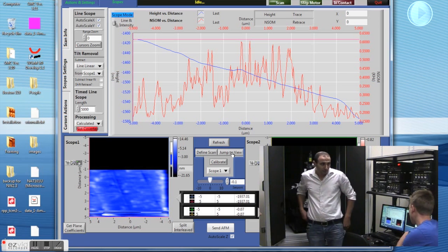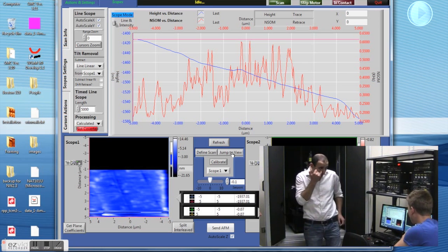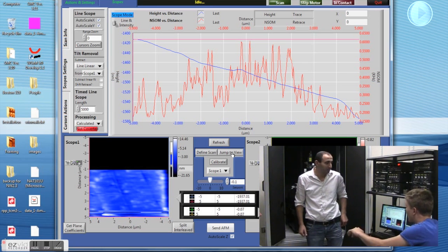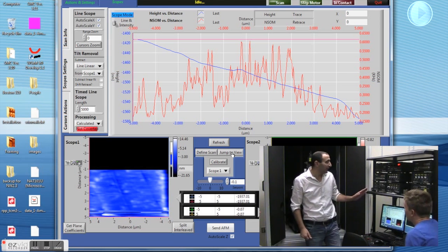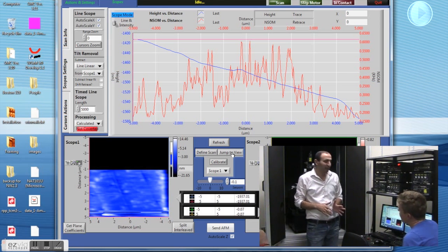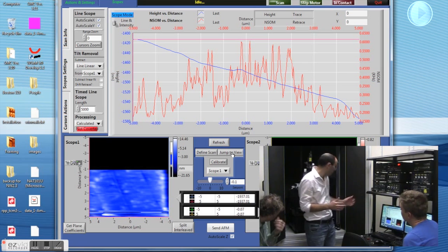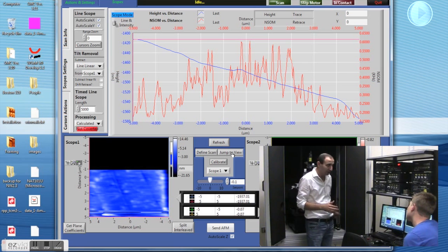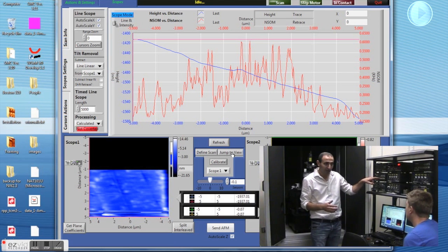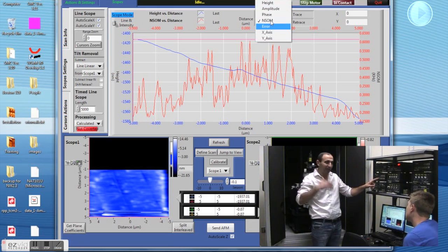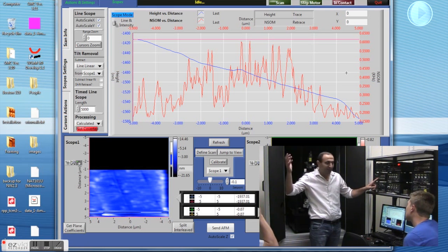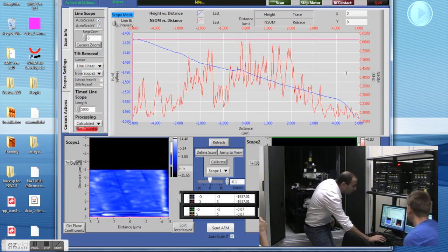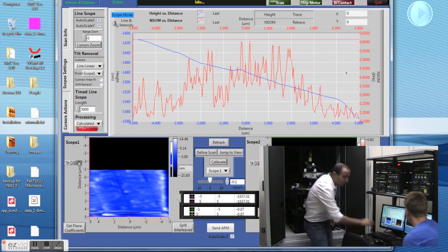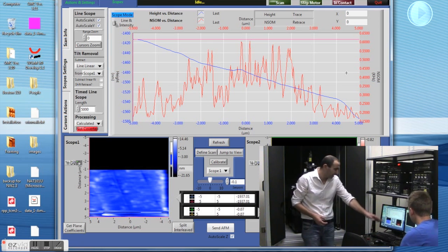Do you record the height and the NSOM with the same tip? At the same time? Same time, for each pixel. From the AFM perspective, the NSOM probe is an AFM tip. It will give you topography images, and you take the signal from the detector and you couple it to an auxiliary input here. So it will be synchronized with the AFM. You could in fact couple other signals like electrical signals or thermal analog signals to the system, and you could choose up to 16 channels and monitor these simultaneously. Okay. So synchronized pixel by pixel.